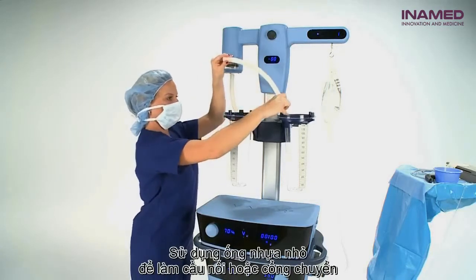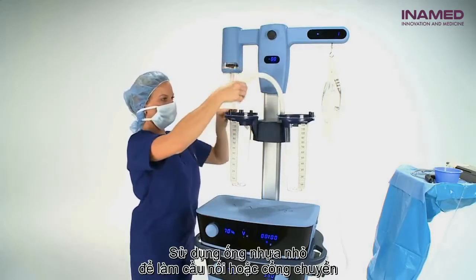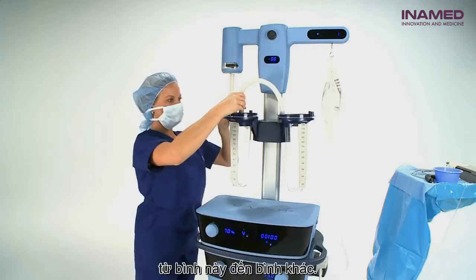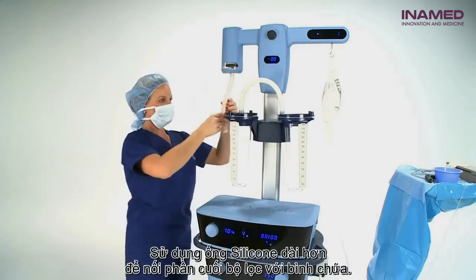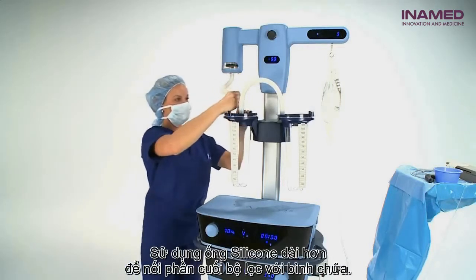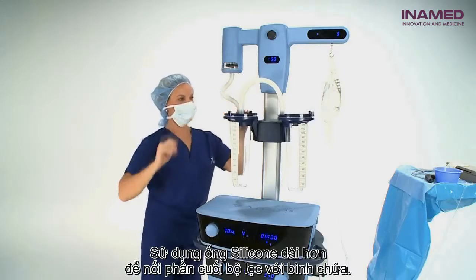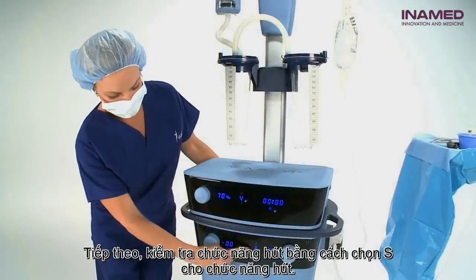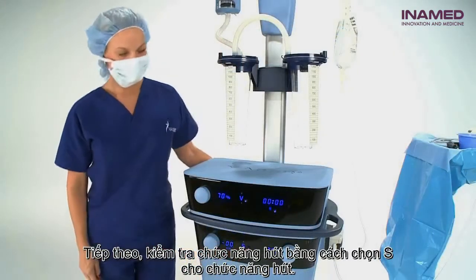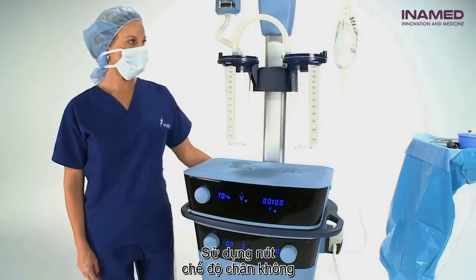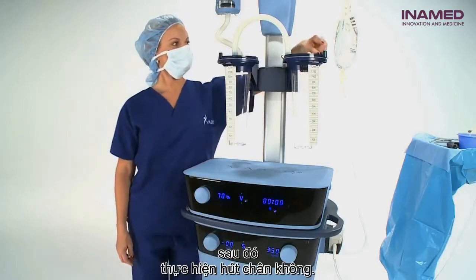Use the smaller silicone tubing piece to bridge or daisy chain from one canister to another. Using the longer silicone tubing piece, attach one end to the filter and the other to the suction canister. Next, test the suction by selecting the S for suction using the vacuum mode button, and then occlude the vacuum.